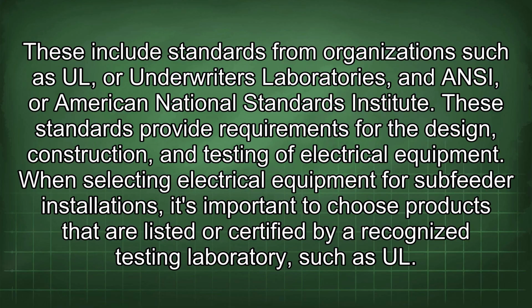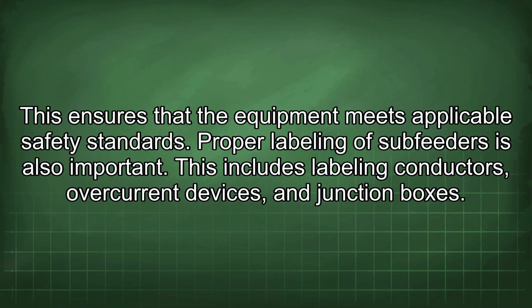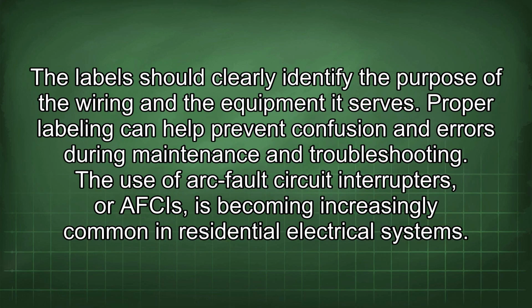When selecting electrical equipment for subfeeder installations, it's important to choose products that are listed or certified by a recognized testing laboratory such as UL. This ensures that the equipment meets applicable safety standards. Proper labeling of subfeeders is also important. This includes labeling conductors, overcurrent devices, and junction boxes. The label should clearly identify the purpose of the wiring and the equipment it serves. Proper labeling can help prevent confusion and errors during maintenance and troubleshooting.